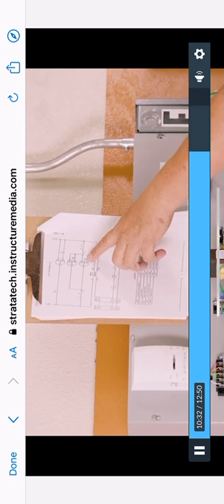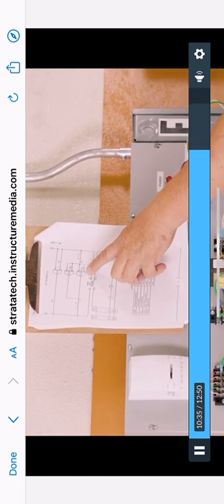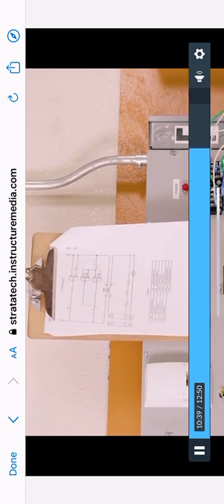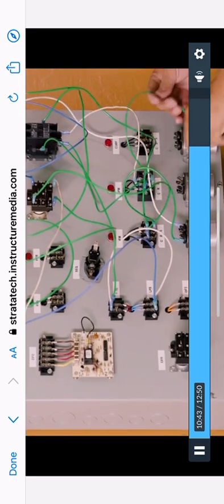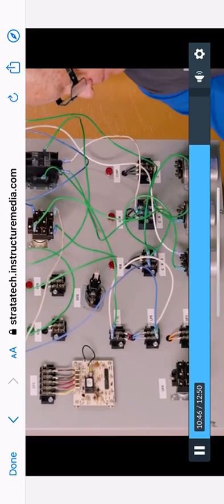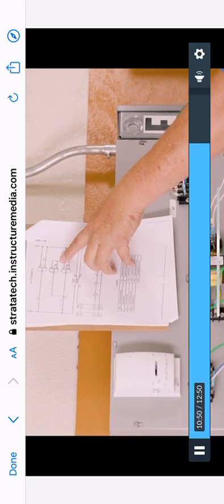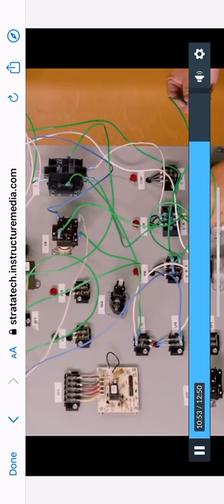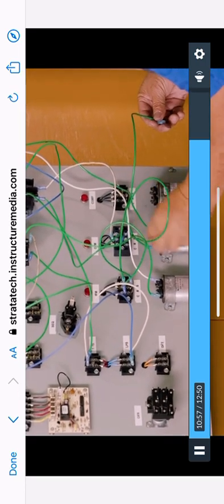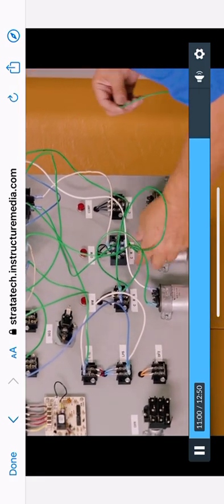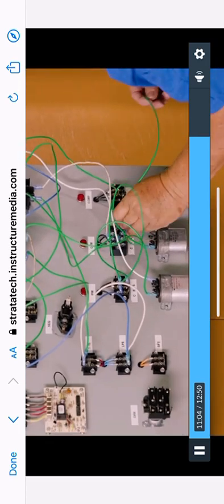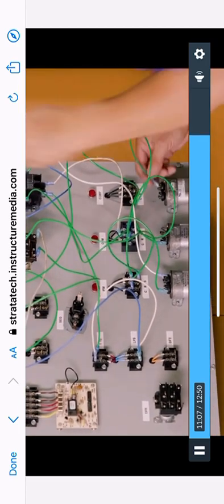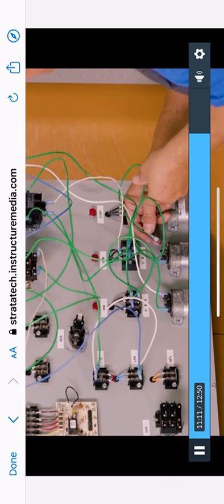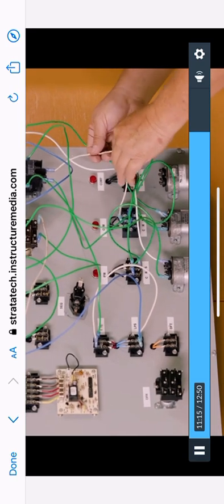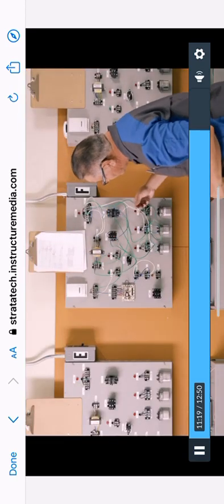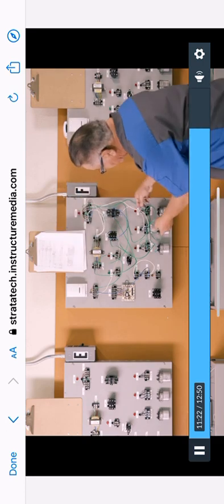I'm going to do my start capacitor. I'm going to go from my S, which is my start on my outdoor fan motor, to one side of my cap. I'm going to come out of my cap, which is what you see on my outdoor fan motor, and I'm going to go to T2. So I'm going to go to the other side of the cap. Okay. So my run's going to go there. And then I'm going to go to my start right here to one side of my cap. Then I got to go back to T2, which I just did on this white wire. So this is all done. The outdoor fan motor is done.